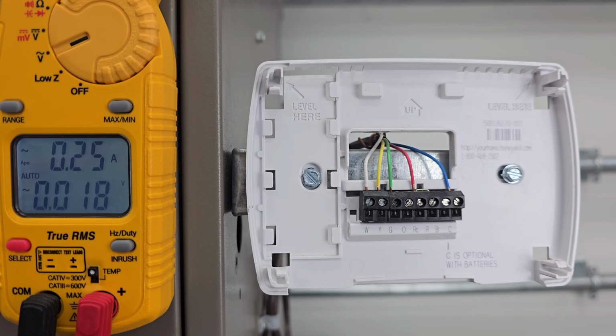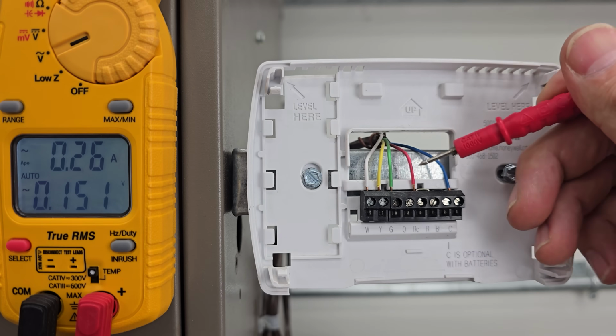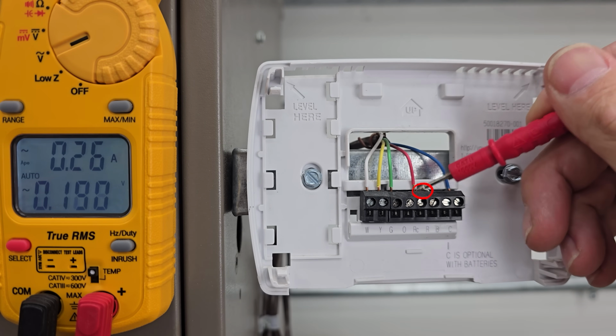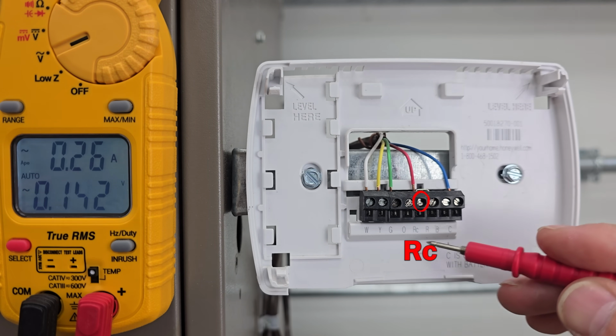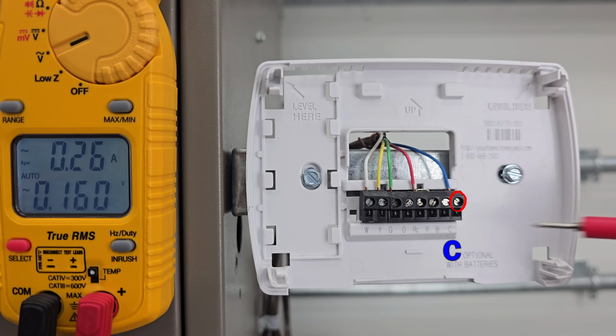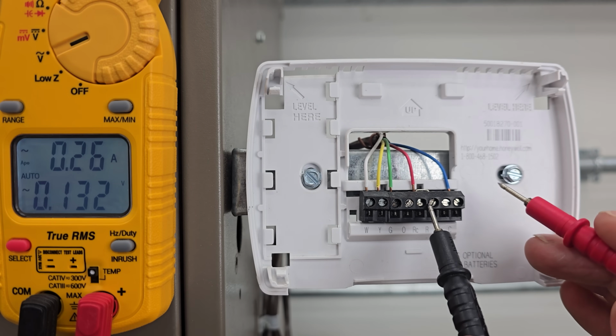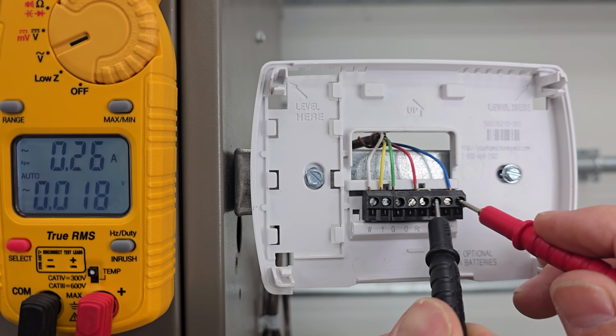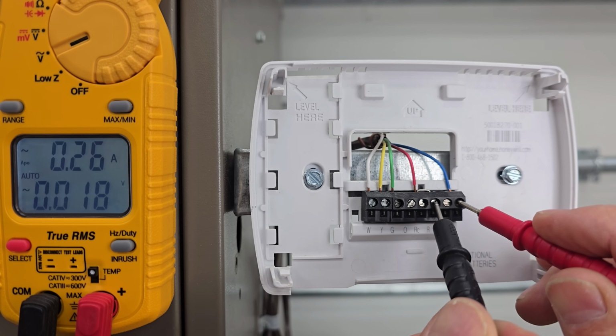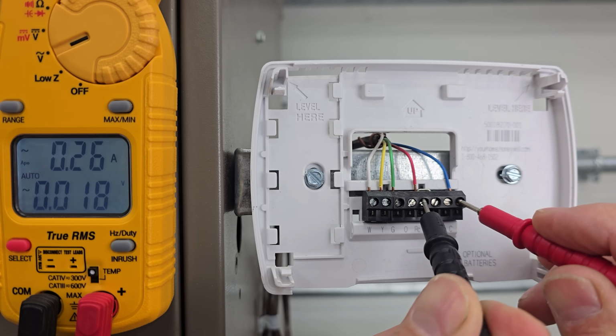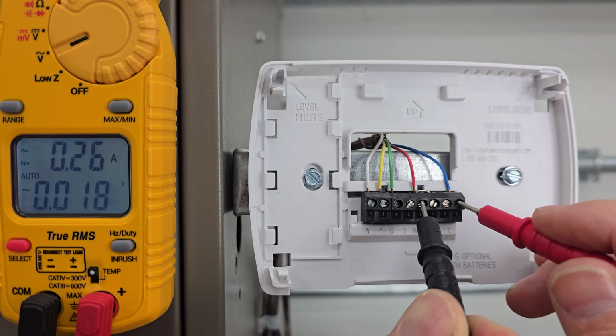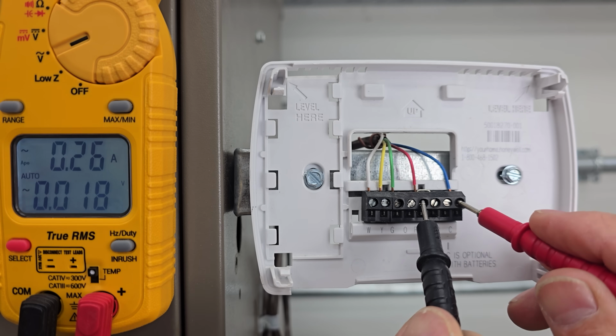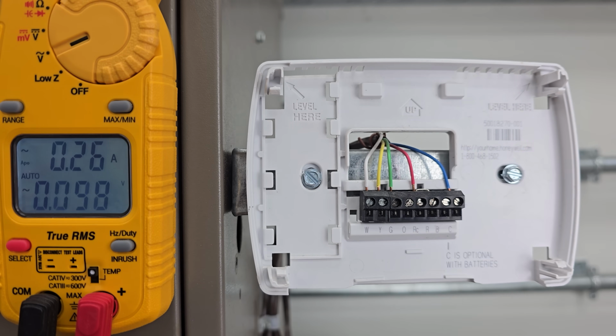You can see our thermostat is blank, and so we need to take off the face, and we're going to locate two terminals. One's going to be the R terminal and one's going to be the C terminal. You also notice, hopefully you can see, that the R to RC has a little jumper there, and so we've got a red wire attached to the RC and we've got a blue wire attached to the C. So we're going to be measuring for 24 volts between the R and the C. It doesn't matter whether we put this left-hand probe in the RC or the R, because there's a jumper, and we need to have 24 volt power here in order to power the thermostat, and you see that we have none. We've got 0 volts there, and so that's the issue.